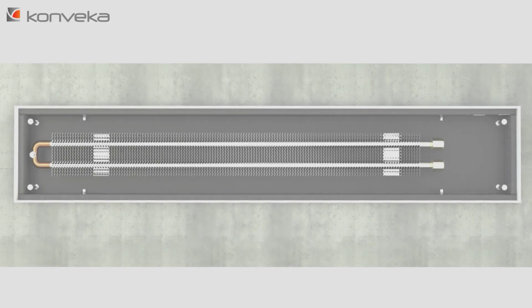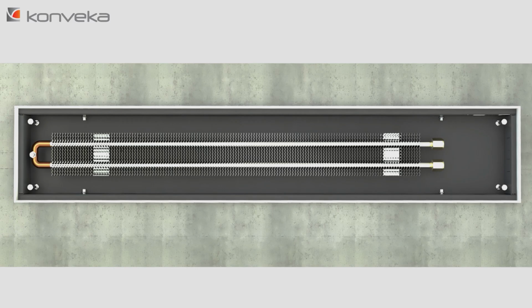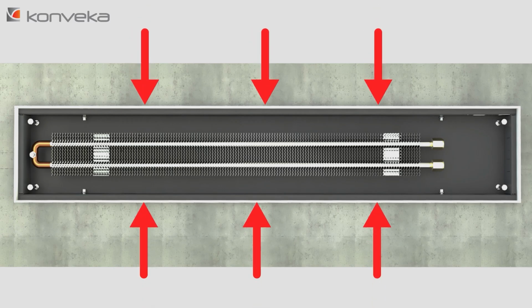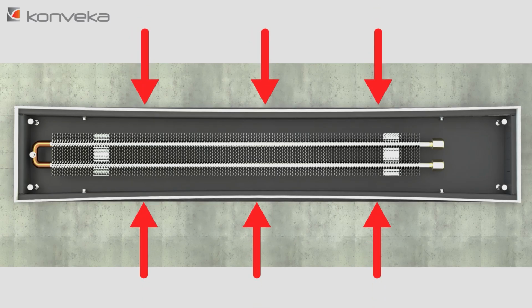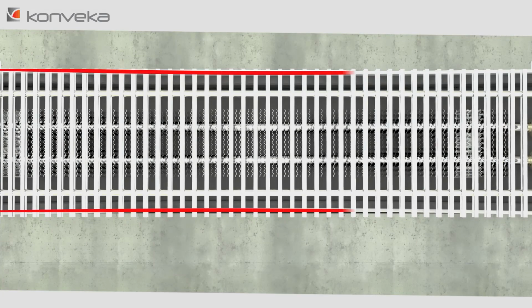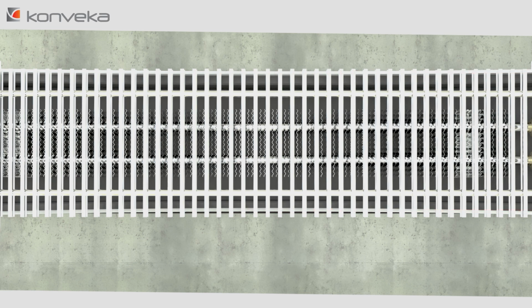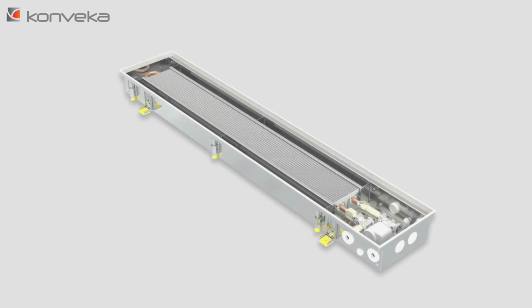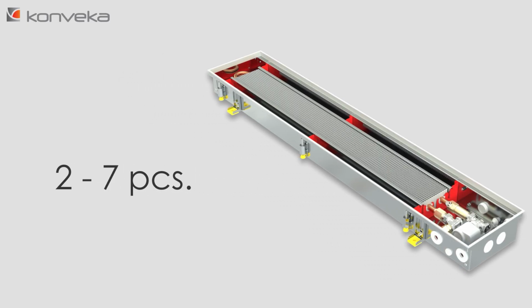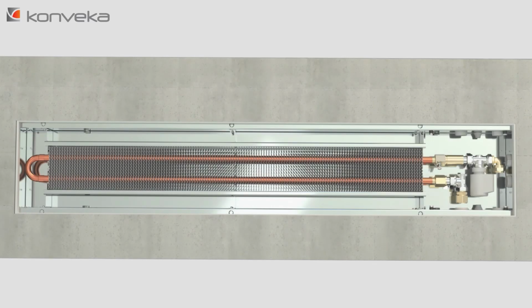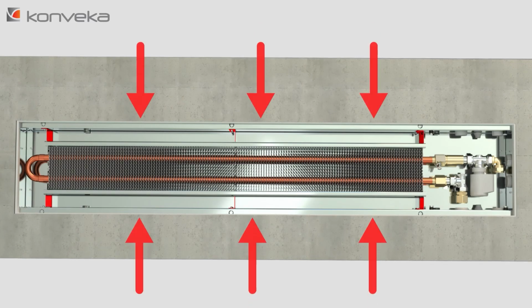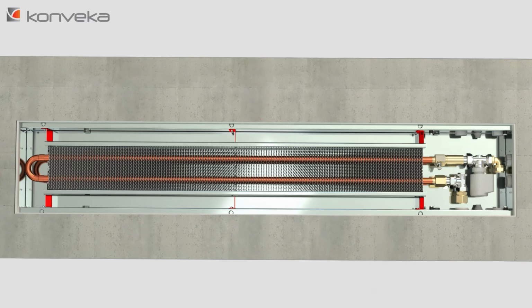Housing rigidity. Usually, trench heaters are mounted inside concrete. Thus, they need to resist the high pressure that results from pouring the concrete. Weak housings will deform under pressure, and later, placing the cover grills becomes impossible. Therefore, we have strengthened our housing with rigid ribs in amounts varying from 2 to 7, depending on the length of the housing. The amount of rigid ribs, together with the resistant material of the housing, ensures the stability of the shape not only during the installation, but also at the time of transportation and operation.